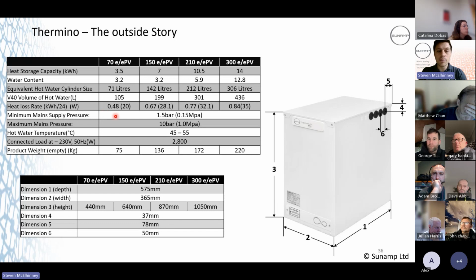Speaking about pressure, minimum supply pressure is 1.5 bar coming into the property, and we've got a maximum of 10. This does annoy me, because we contradict that slightly by saying if you're exceeding 5 bar coming into the property, or you think the property is at risk of exceeding 5 bar, you should put a pressure regulating valve on your water supply to limit that pressure to 5 bar. What we're saying here is the heat exchanger can take 10 bar.